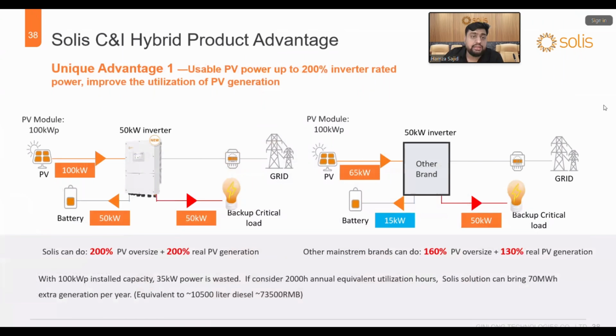First thing is unique advantage number 1, usable PV up to 200% of inverter rated power, which improves the utilization of the PV generation. As you can see, if the Solis inverter has 100 kilowatt PV installed, 50 kilowatt at the same time can charge the battery and 50 kilowatt supports the load. So this makes it different from the other inverters available in the market. So it can use PV power up to 200% of the rated power. In other brands, if 65 kilowatt is available with the 50 kilowatt inverter, they can only charge the battery with 15 kilowatt and support the backup load with 50 kilowatt. So Solis can do 200% PV oversize plus real PV generation. Other mainstream brands can do 160% oversize plus 130% real PV generation.